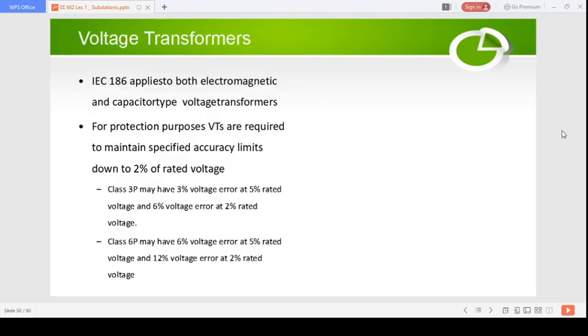Next we are going to talk about the voltage transformers. IEC 186 talks about both the electromagnetic and capacitor type voltage transformers. For protection purposes, voltage transformers are required to maintain specified accuracy limits down to 2% of rated voltage. So for protection purposes, the VT, what we sometimes call the PT, the potential transformer, is required to maintain this accuracy limit down to 2% of the rated voltage.